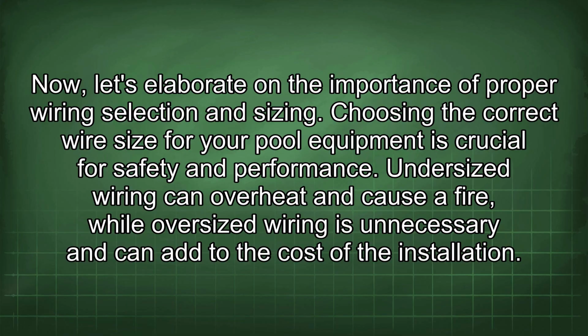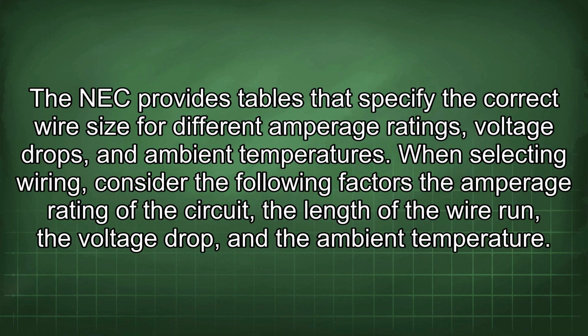Choosing the correct wire size for your pool equipment is crucial for safety and performance. Undersized wiring can overheat and cause a fire, while oversized wiring is unnecessary and can add to the cost of the installation. The NEC provides tables that specify the correct wire size for different amperage ratings, voltage drops, and ambient temperatures. When selecting wiring, consider the following factors: the amperage rating of the circuit, the length of the wire run, the voltage drop, and the ambient temperature.